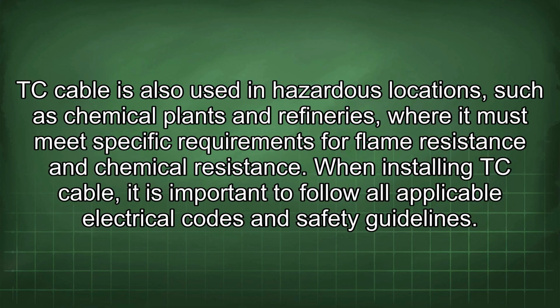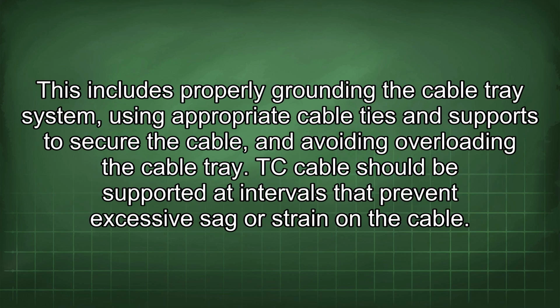TC cable is also used in hazardous locations such as chemical plants and refineries, where it must meet specific requirements for flame resistance and chemical resistance. When installing TC cable, it is important to follow all applicable electrical codes and safety guidelines. This includes properly grounding the cable tray system, using appropriate cable ties and supports to secure the cable, and avoiding overloading the cable tray. TC cable should be supported at intervals that prevent excessive sag or strain on the cable.